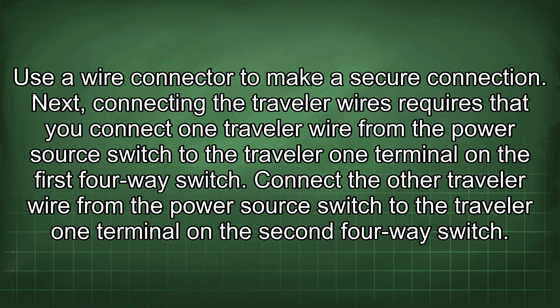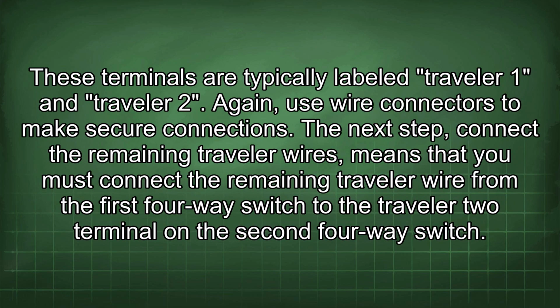Next, connecting the traveler wires requires that you connect one traveler wire from the power source switch to the traveler 1 terminal on the first 4-way switch. Connect the other traveler wire from the power source switch to the traveler 1 terminal on the second 4-way switch. These terminals are typically labeled traveler 1 and traveler 2. Again, use wire connectors to make secure connections.